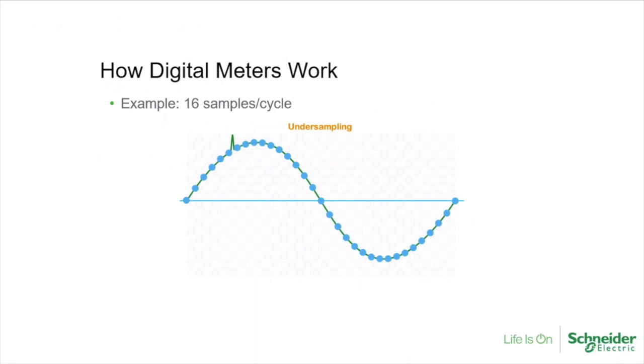So this is an example of how digital meters work. Most meters, or all meters today, have a digital signal processor that collects data from your analog inputs in real time. That digital signal processor samples the event at 128, 256, up to 1024 samples per cycle. And we actually have meters today designed specifically for transients that can get up to 150, 167 samples per cycle. And I think there are some that are even higher than that.